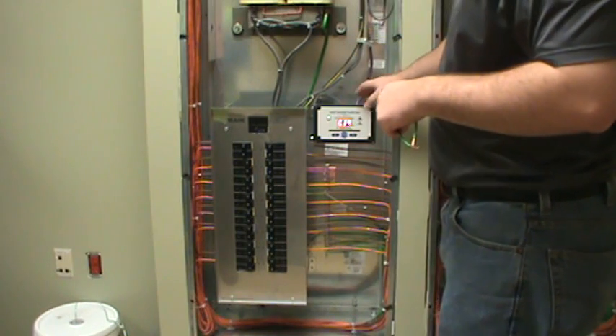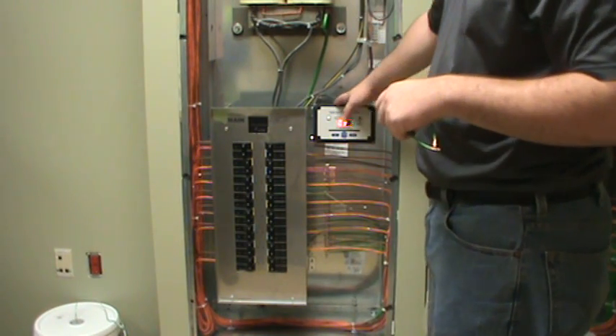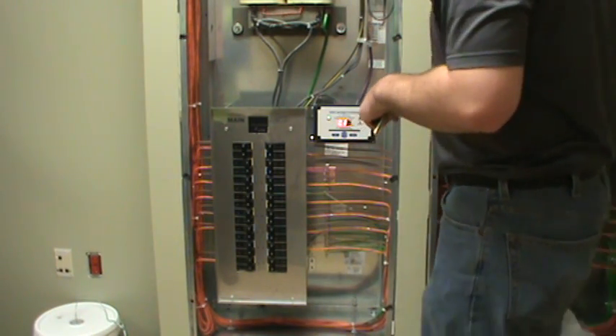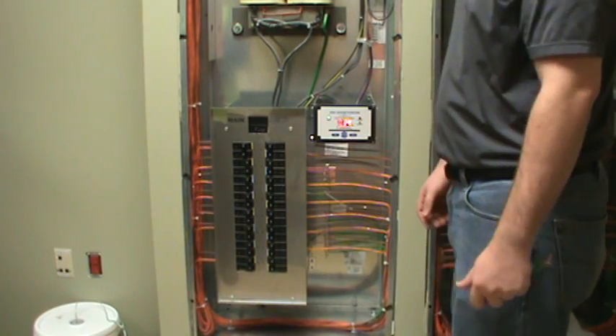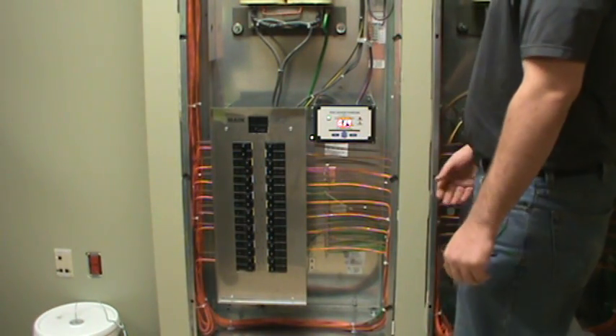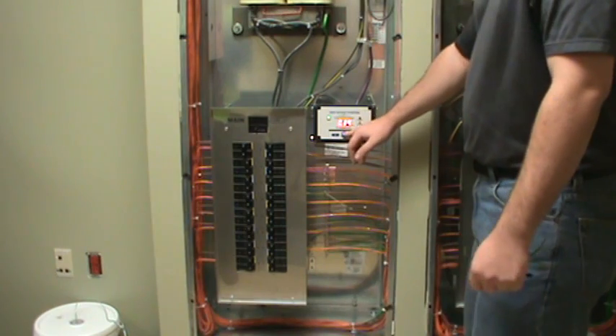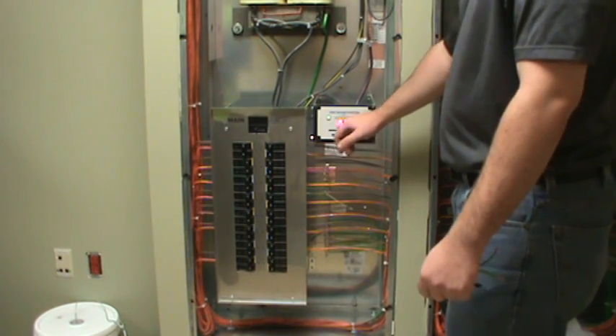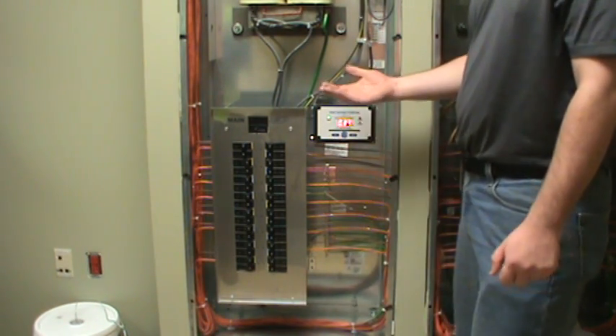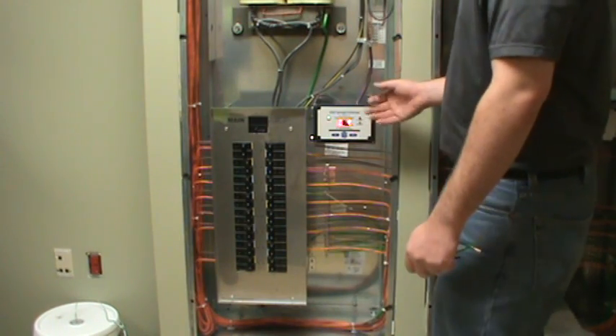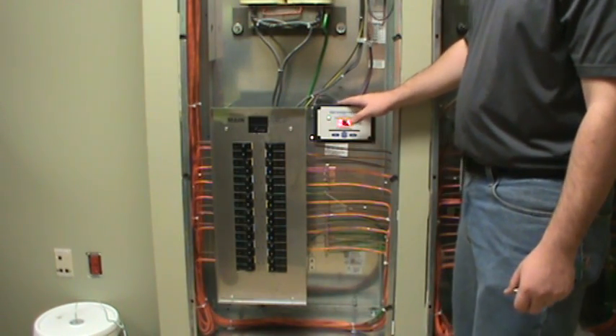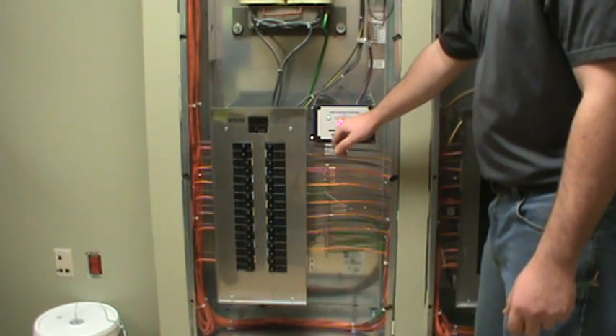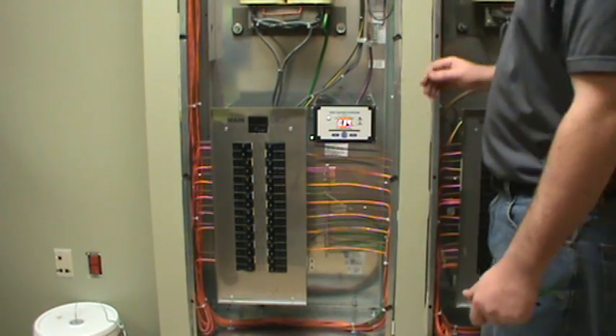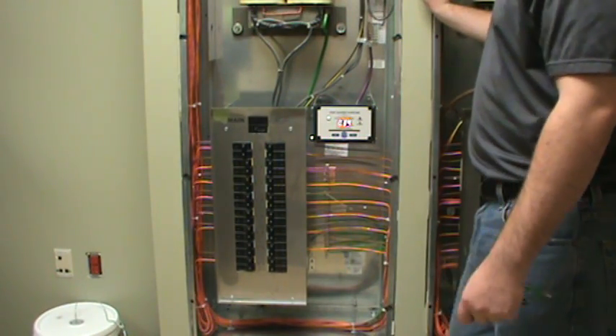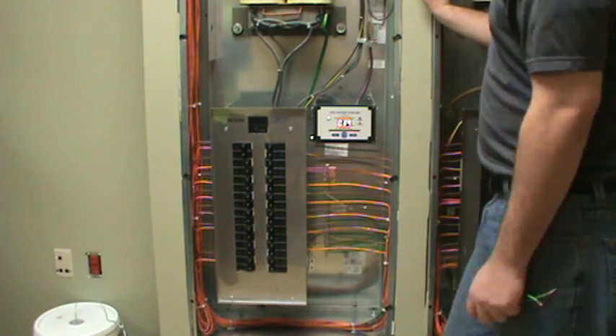This here is our LIM, line isolation monitor. What this is doing is measuring line-to-line voltage and also measuring line-to-ground impedance. And with that, it can do a calculation, just using Ohm's law, of how much current we have going through ground. That's exactly what we're monitoring here. Right now, we don't have anything powered by the system. We have 0.39 milliamps in ground. It's a nice low number.